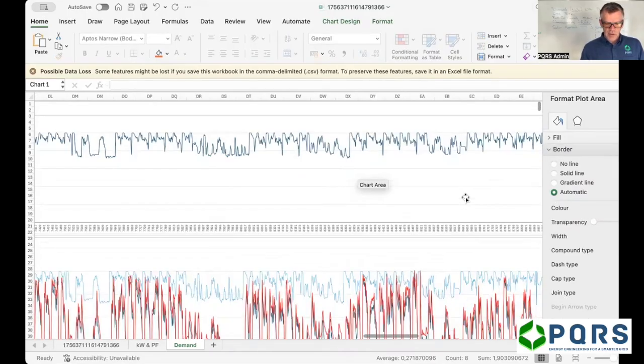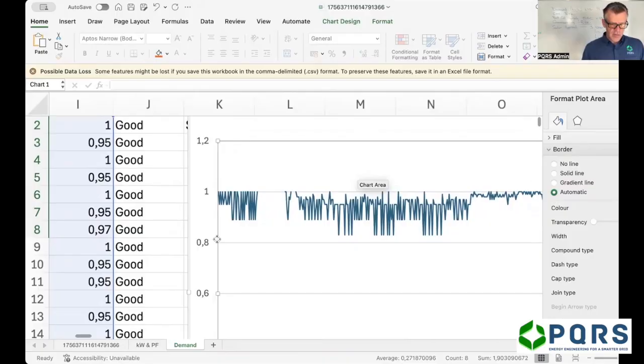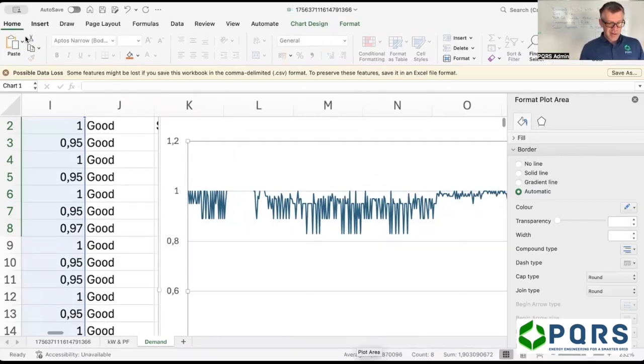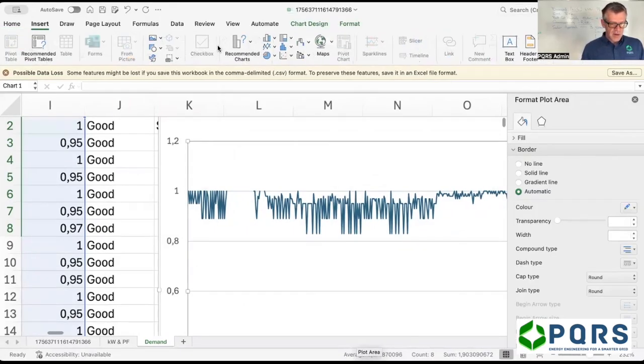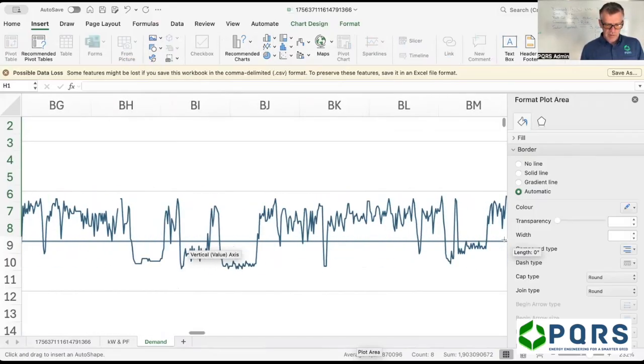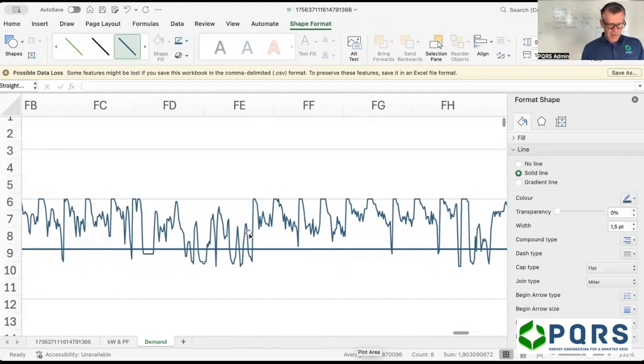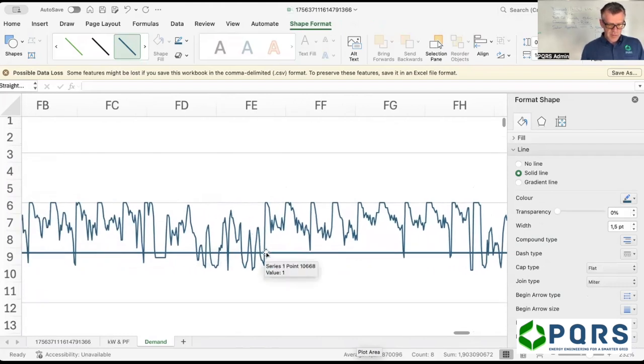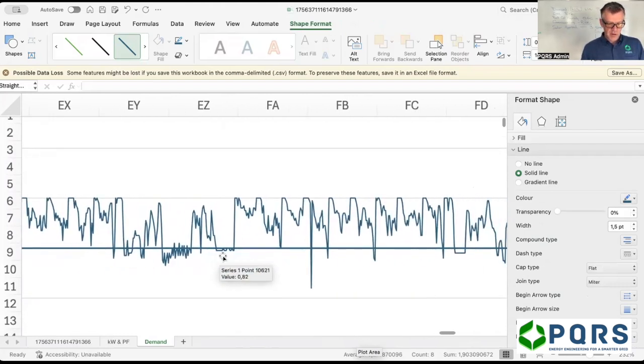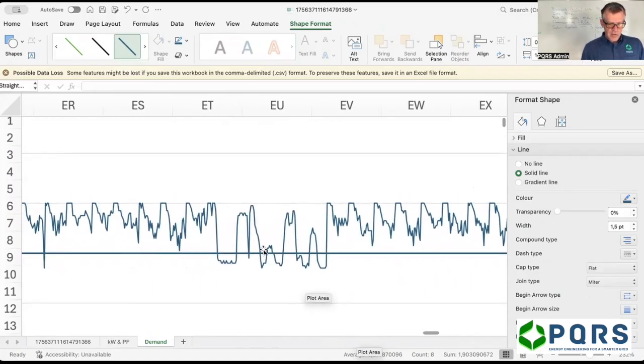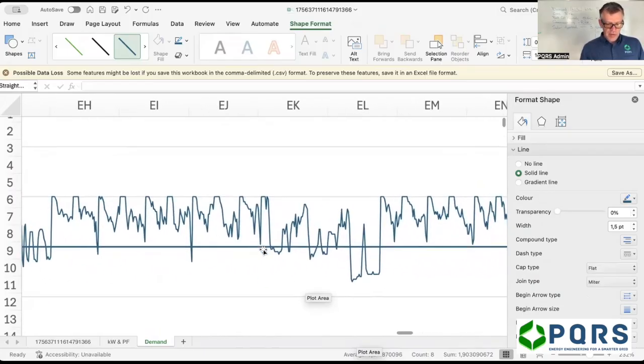So if I zoom out a bit, that's for the entire year. This line over here represents 0.8. If you have a power factor of 0.9, that is pretty adequate. If we add a line, that line is 0.8. You can see over weekends, wherever the top line crosses the bottom line, it goes below 0.8 there. What's that, 0.64? So this is going to cause issues when you have a solar system installed.